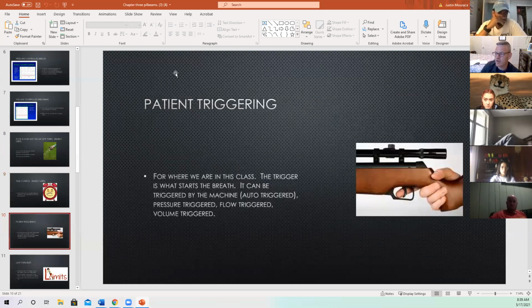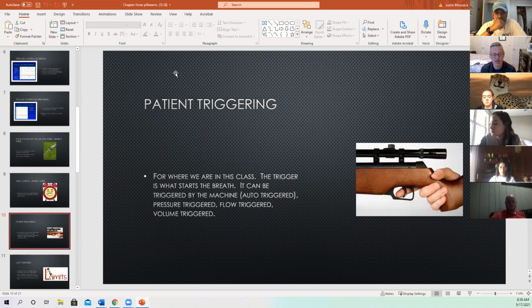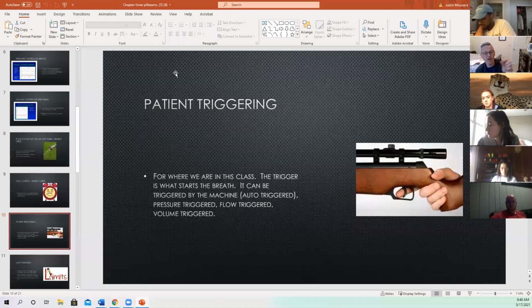So, flow triggering. Anybody who's been in the ICU, even on their floor rotation, walking through the ICU or getting to hang out in there, we realize that the patient either triggers the ventilator or the ventilator triggers the ventilator, right? It's one or the other. Then we have to realize how it's actually being triggered, right? And there's different ways of triggering a ventilator. Like if the patient generates a negative flow, that pulls flow off the system. There's a bias flow running through the ventilator. So there's constant flow running through that circuit at all times.